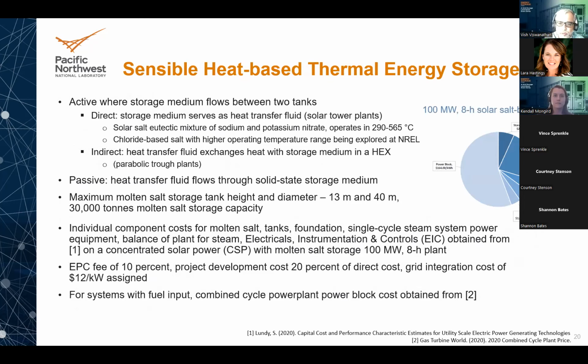This formed a foundation for how we costed out a sensible heat storage system that has a steam power plant, for example. There are different types of sensible heat: active heat, passive heat. Active has direct, when the storage medium serves as the heat transfer fluid. Indirect is when the heat transfer fluid exchanges heat with the storage medium. Active is when the storage medium actually flows between the tanks. Passive is when the heat transfer fluid flows through the storage medium, such as, say, concrete. And you have hot air flowing through pipes in the concrete, for example.